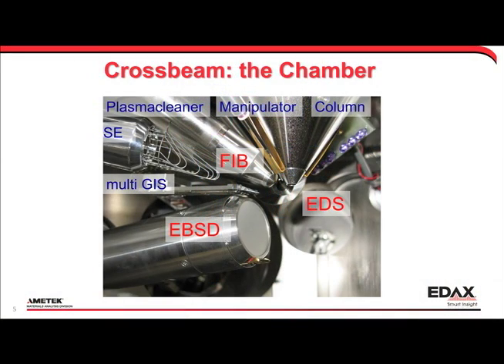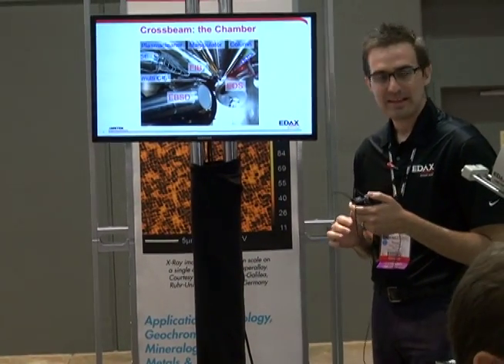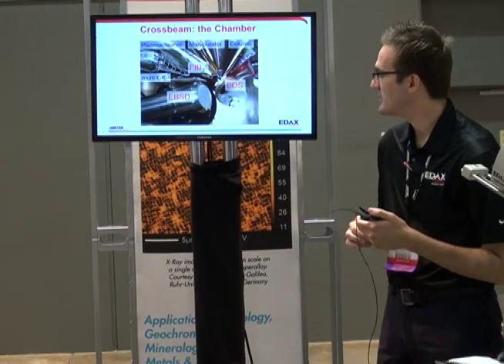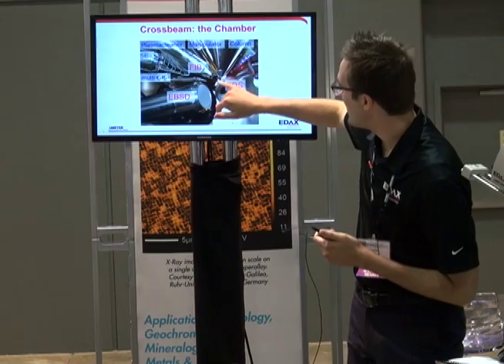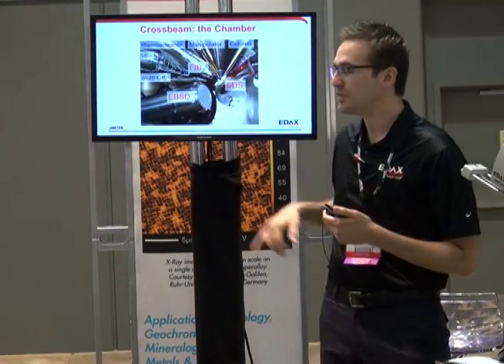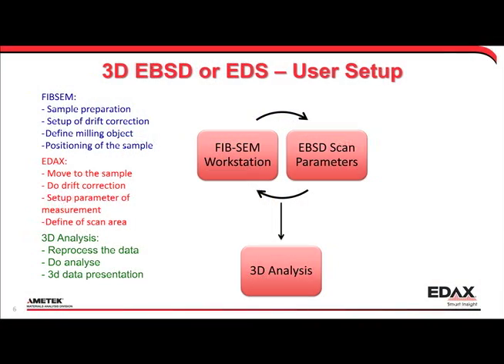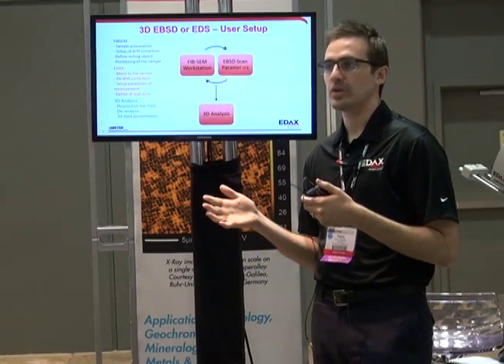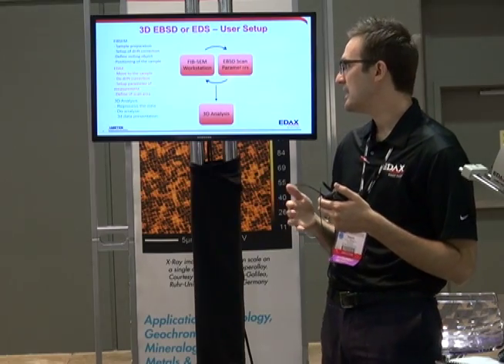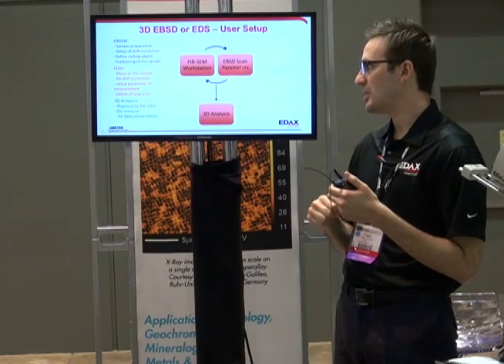We'll have a short presentation showing what happens in the FIB. Here's a quick view of what the inside of a FIB-SEM might look like — quite crowded. The EDS detector is right back here, and the EBSD detector is there as well; you can do 3D in both. With 3D, there's a back-and-forth exchange between the microscope and the EDAX software — one controls the milling, one controls the scanning and EDS data collection. Once you've gotten all your slices, you jump out of that loop and into the analysis process.